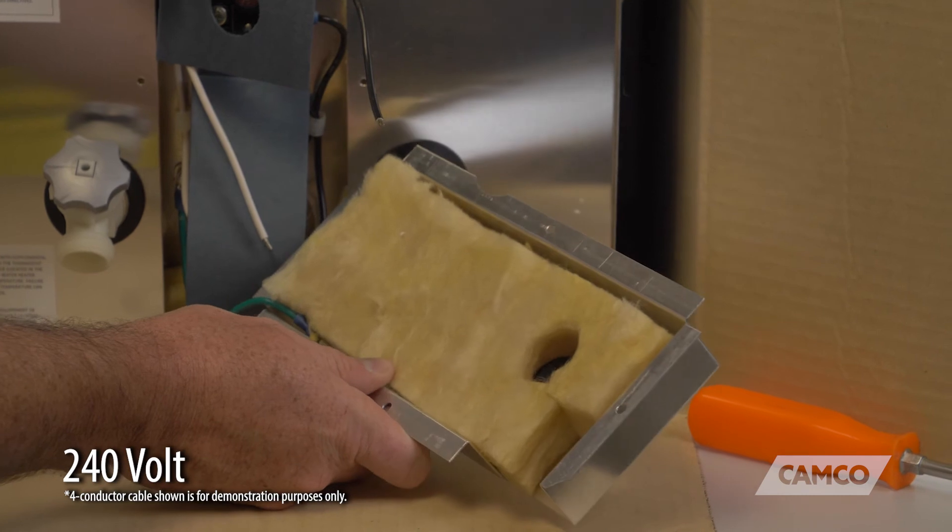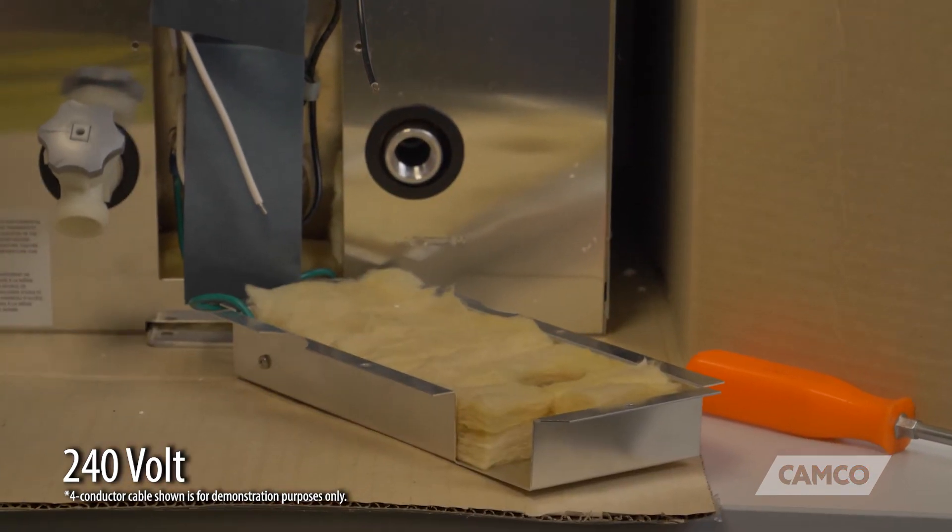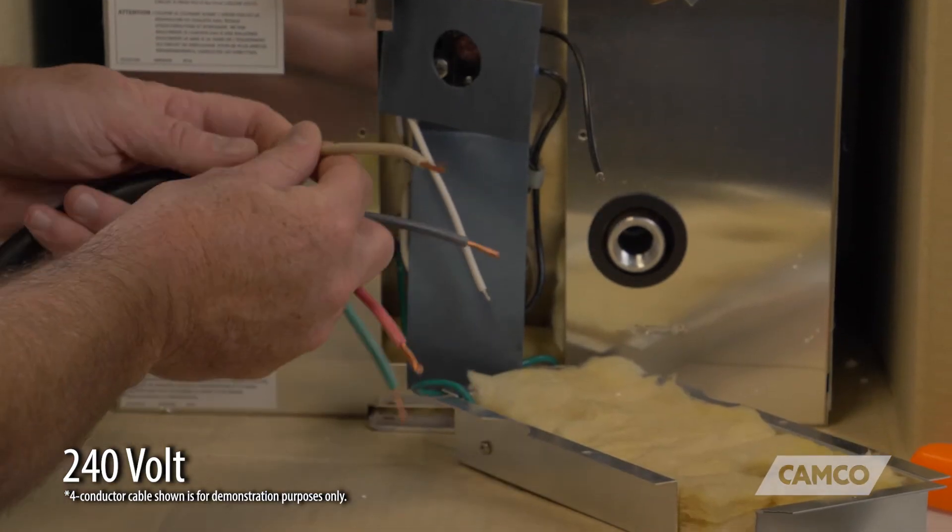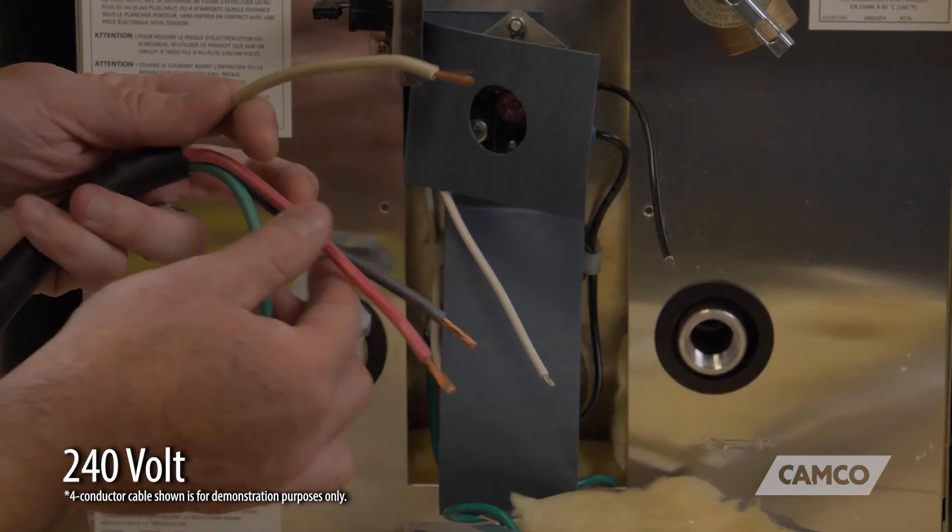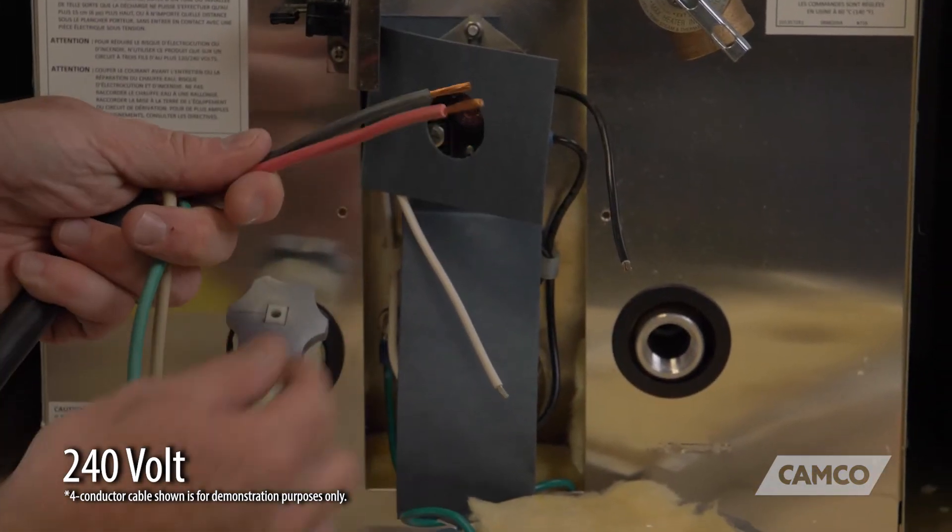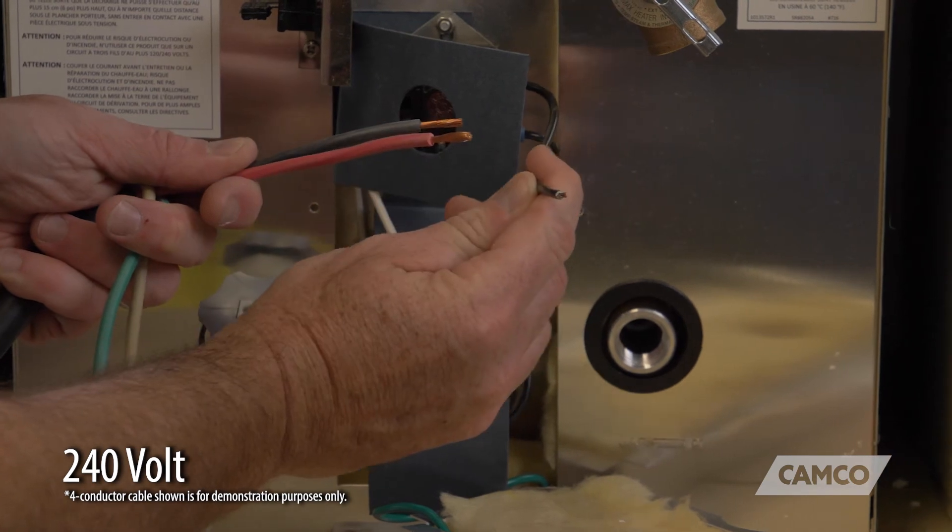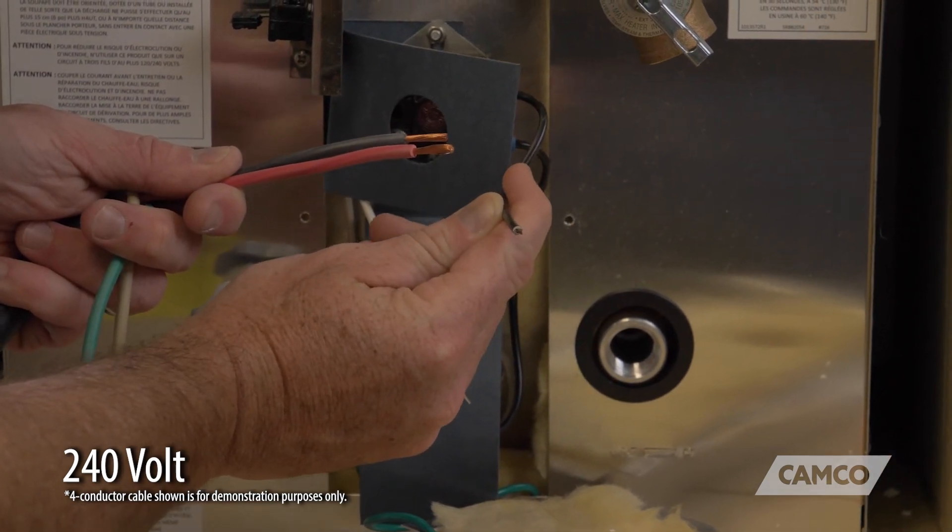We're going to connect our white to the loose white wire, and we're going to connect the black and red hot wires to the black hot wire coming off of the water heater.